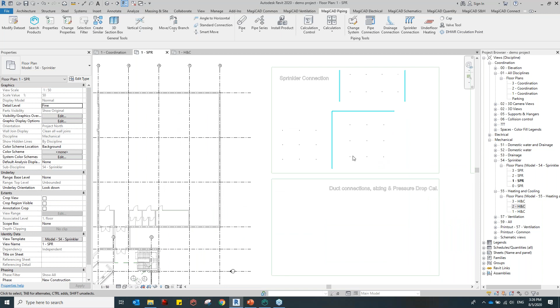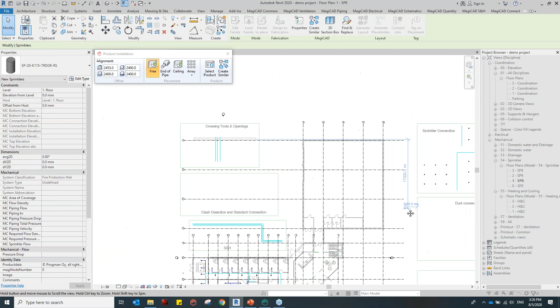Let's take the example of sprinklers. If I want to install a sprinkler at 2.4 meters, I'll put it in the course so you can see the 2D symbols. I'll use this sprinkler, create similar, and arrange sprinklers inside this room. I specify my height, coverage area, design density, and required pressure. For example, for 1000 millibar, which is 1 bar, I specify the required pressure as 1 bar.